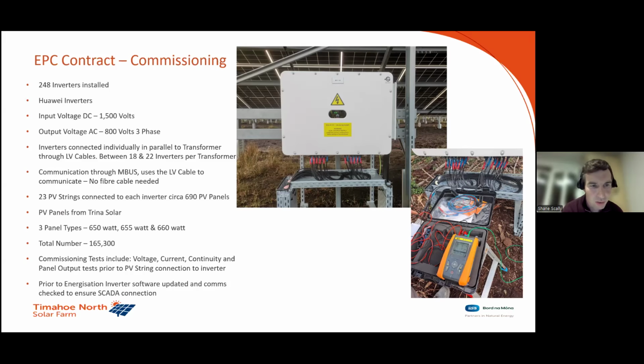There's around 23 PV strings connected to each inverter, so about 690 PV panels per inverter. If you multiply that by the 248, you're not going to get 165,300 exactly, since some are sized differently depending on the layout of the particular inverter. All the PV panels come from Trina.